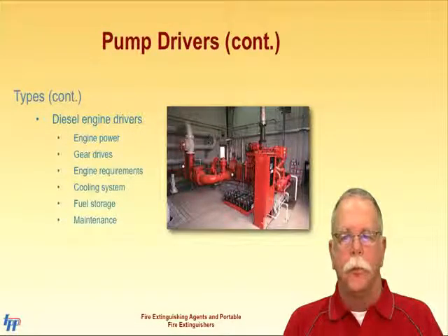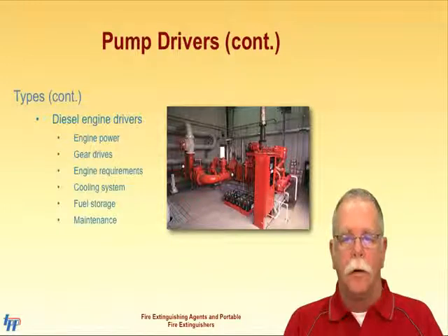Diesel engines are the most dependable internal combustion drive mechanism for a fire pump application and have the advantage over electric drive motors in that they don't need an external power source for operation. However, for a vertical shaft pump, a gear drive is required to change the angle of drive from engine to impeller shaft. One advantage of using a gear drive is that a gear ratio may be used to attain proper pump speed without running the engine too slow or too fast.